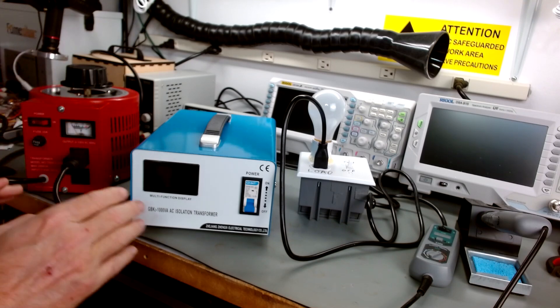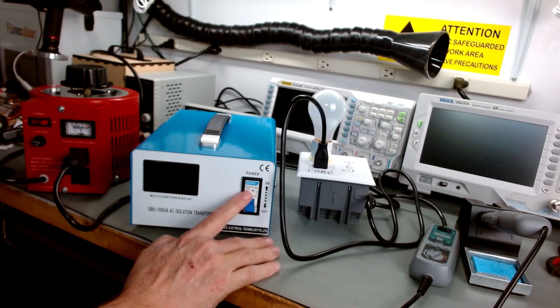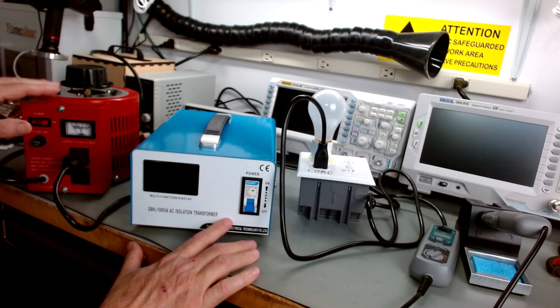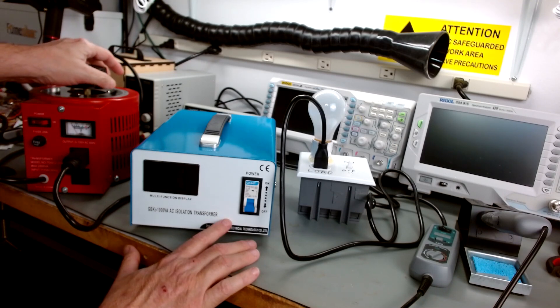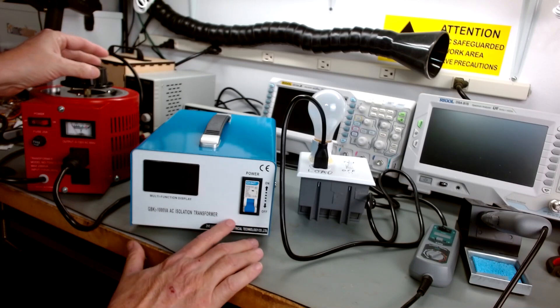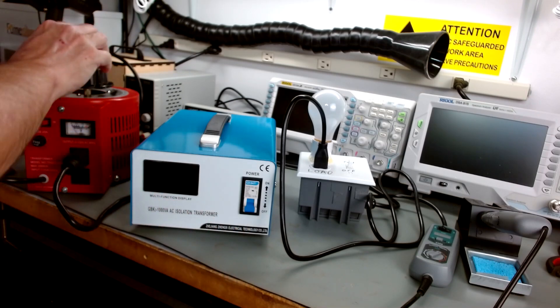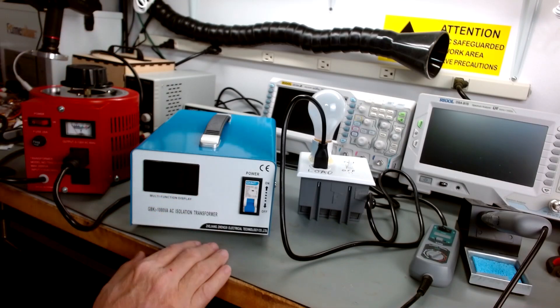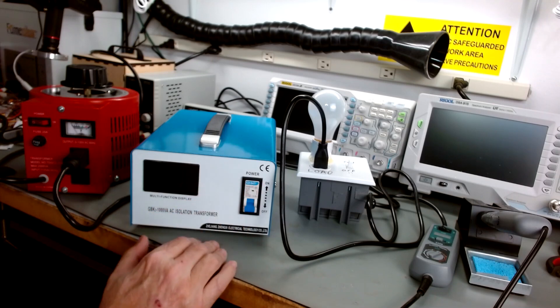The reason that's not going to happen is because the isolation transformer has a circuit breaker in it and that circuit breaker is rated at 10 amps. So the most that I could pull without popping a circuit breaker would be 10 amps out of this unit. So since the winding is rated at 20, at any voltage that I put it at, I should be safe at 10 amps because maybe I could pull more than 20 amps at a low voltage, but not if a circuit breaker is on that system.